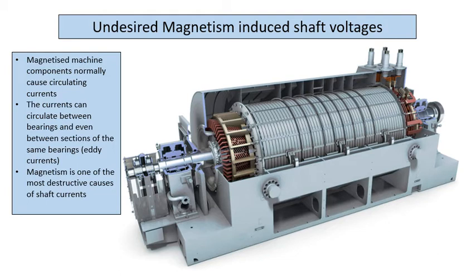Other causes I've already put: electrostatic, turbines, wet steam fans. And then I said, yeah, standard high-speed motor drives. That's what I was saying about that. You can have a standard drive, and if you don't have some form of shaft grounding, you can have a significant amount of electrostatic voltage build-up on the shaft. So you need to do something. And this is a typical installation where, why only put one set of brushes here in one place? Yeah, Peter's answered with his head.